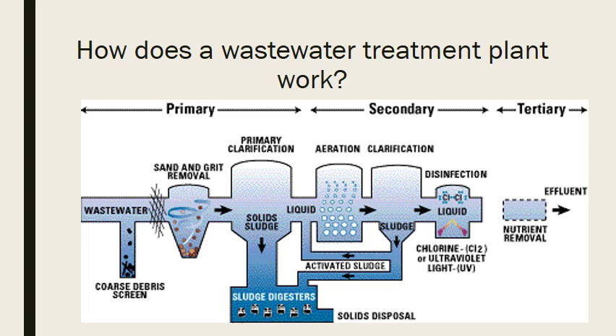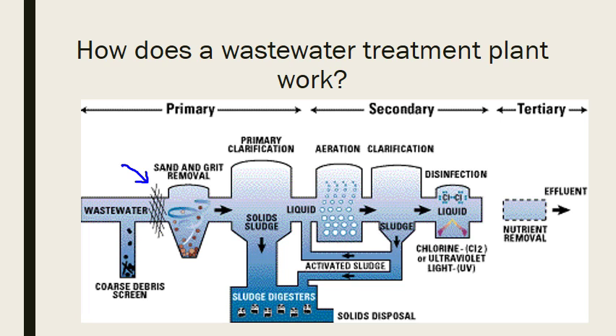Here is a typical diagram of what a wastewater treatment plant looks like — it is displayed as an animated GIF. In primary treatment, the first step is the bar screen. Liquid flows through pipes and hits the bar screen; anything too big settles out as coarse debris at the bottom. The next stage is sand and grit removal, where the tank is agitated to allow larger materials — sand, grit, dirt, and other soil-like particles — to settle out.